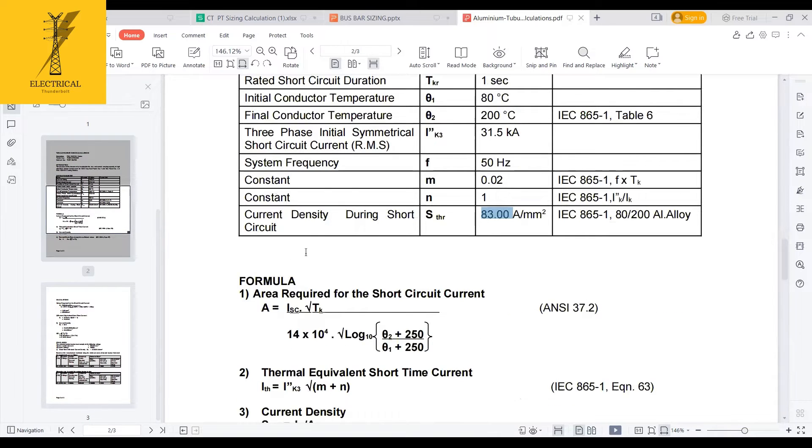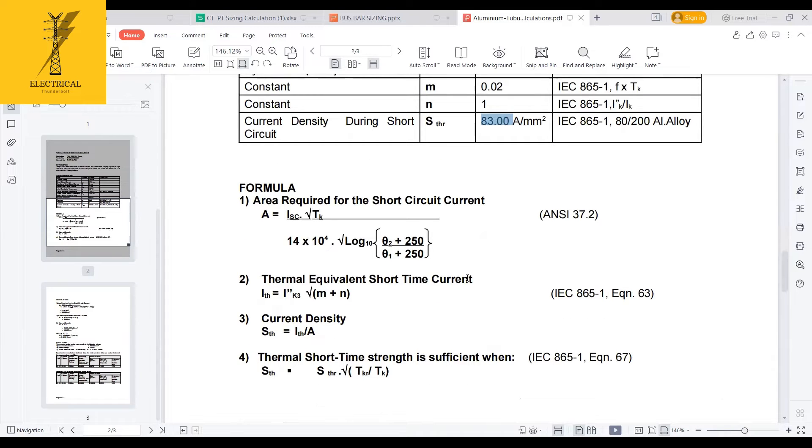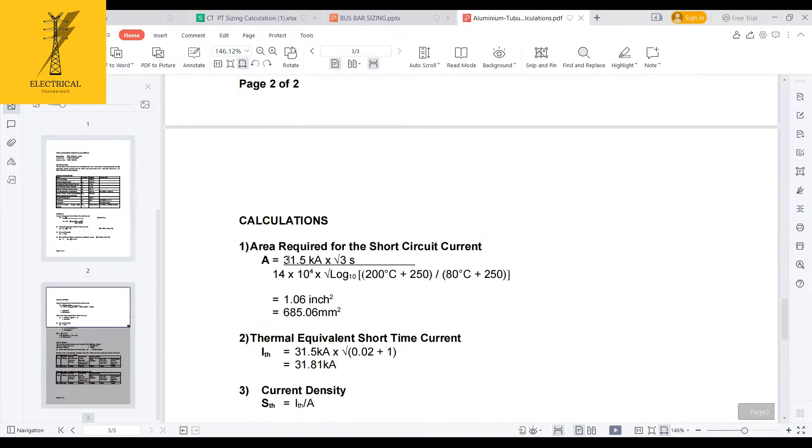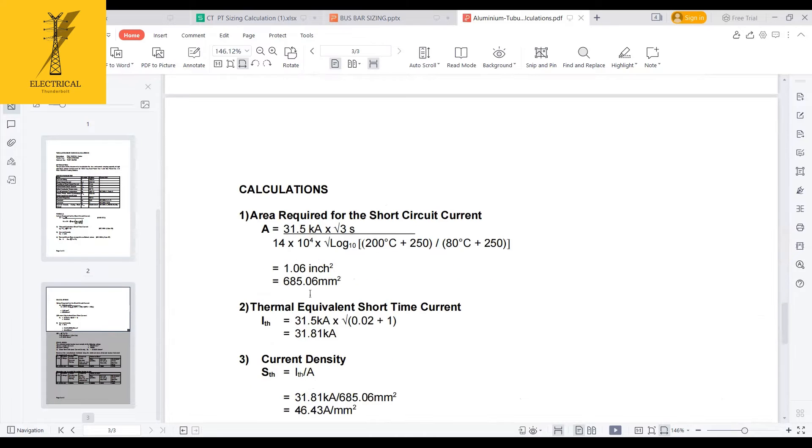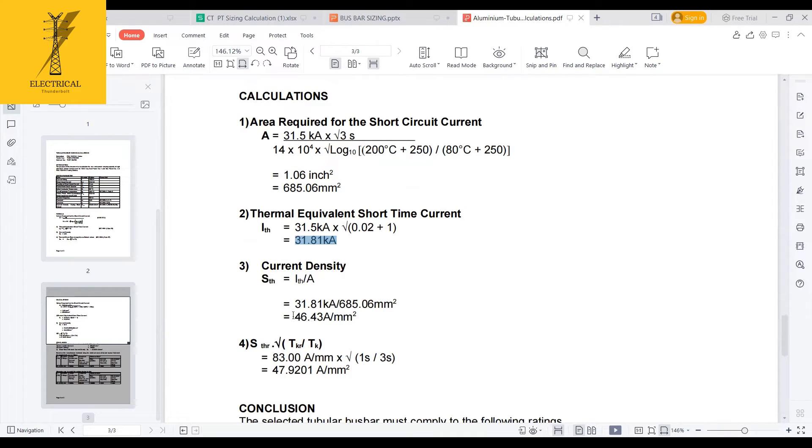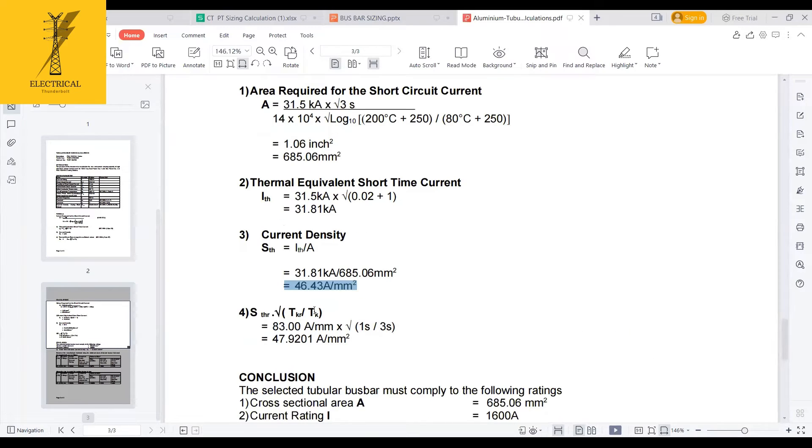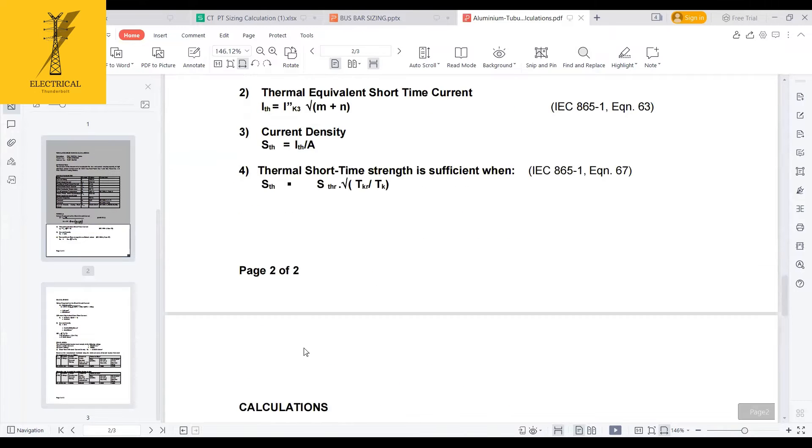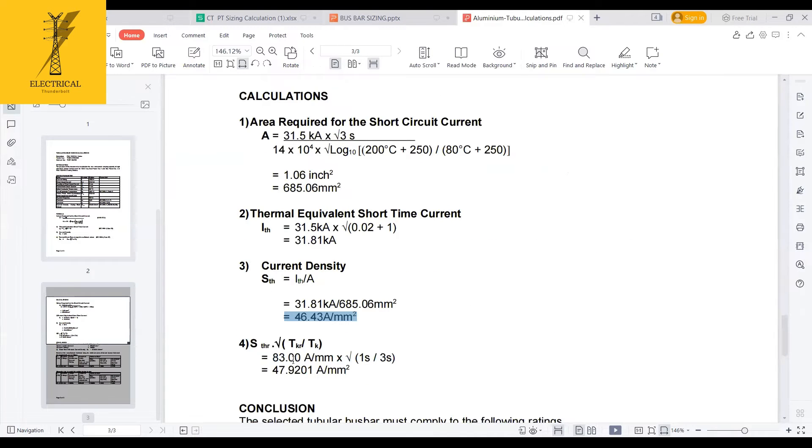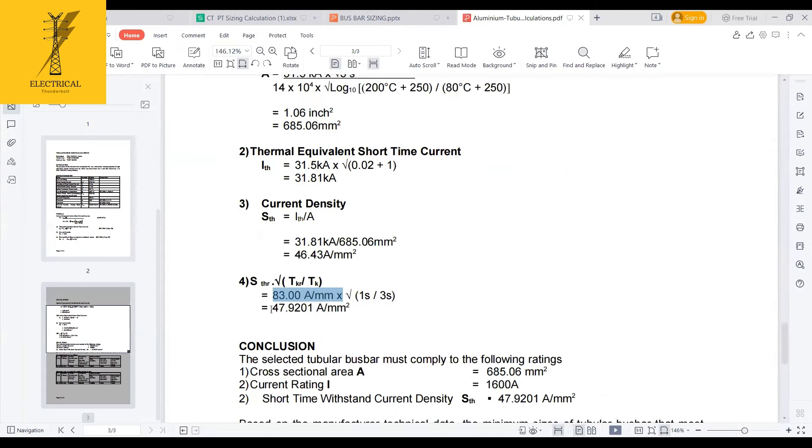Now I am calculating the area required for short circuit current and thermal equivalent short circuit current, current density. Let me see if thermal short time strength is sufficient. Now let's see, I am calculating the area required. So here I require 685.06 mm square minimum conductor, aluminum conductor. And thermal equivalent short term current I calculated, which is 31.81. And 31.81 divided by this will give me the current density, which is 46.